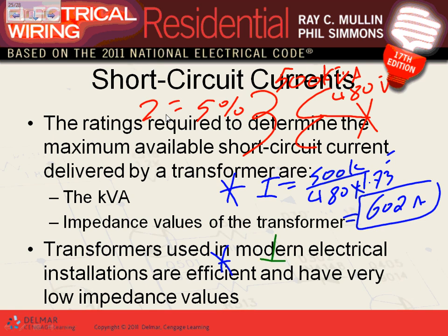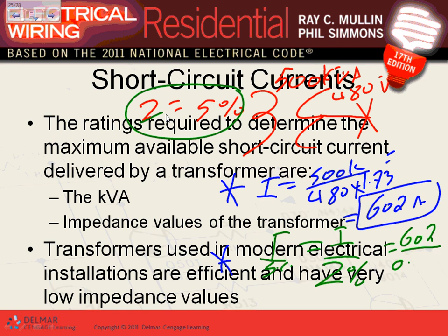then you take the I short circuit: take the I, divide it by the Z, the impedance. What does that mean, Chad? Take the 602, divide this by the impedance. What's the impedance? The impedance is right here, Z, which is 0.05. Press, please. 12,000 amps. That's it.